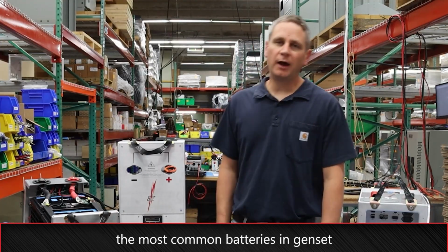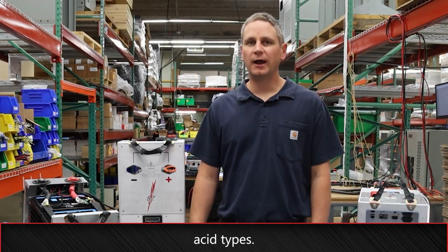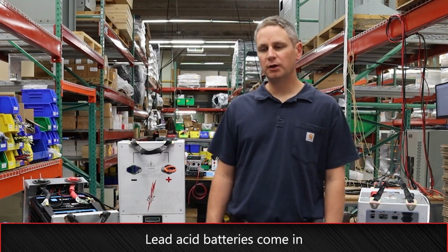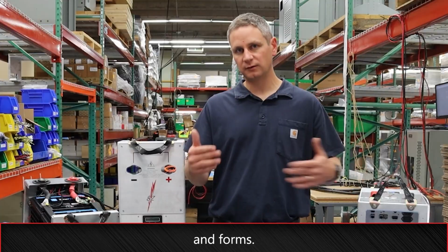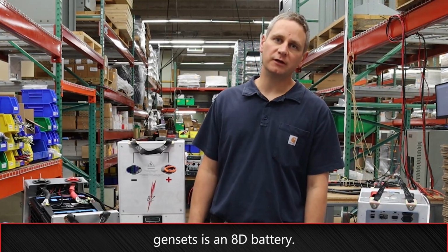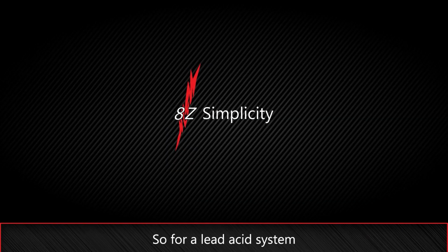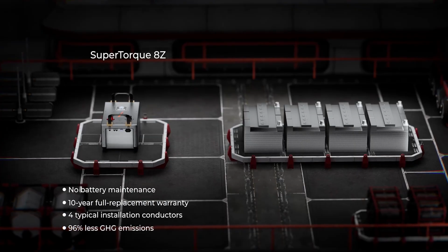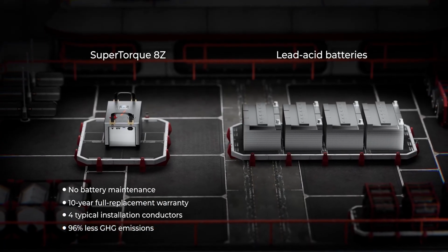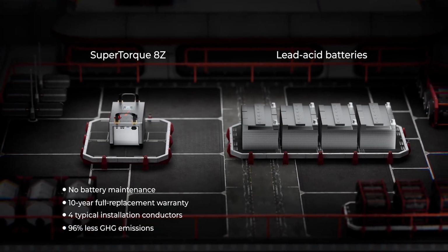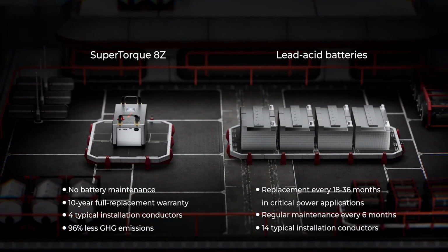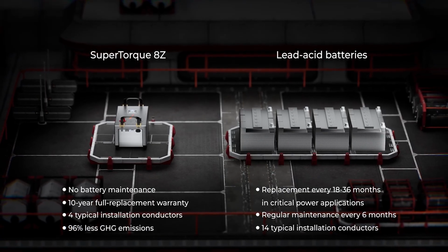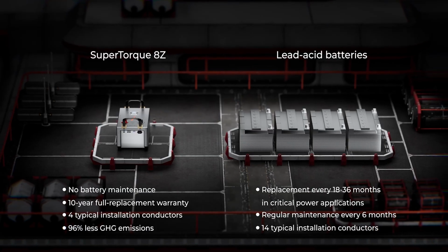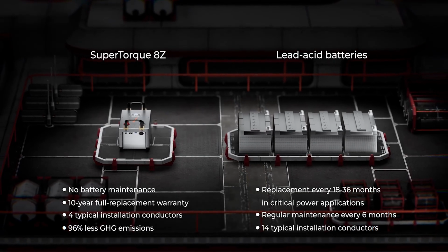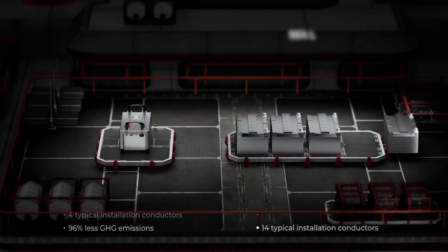So today, the most common batteries in genset starting applications are lead acid type. Lead acid batteries come in an array of different sizes and forms. The most common for large gensets is an 8D battery. So for a lead acid system today, you'll have to purchase 4 batteries and install those batteries and commission them in the application. You'll also have to purchase between a 20 amp and a 50 amp battery charger for those lead acid batteries. That whole system will need to be calibrated, configured, and deployed into the field. For the SuperTorque 8Z, all of that functionality is provided in one unit.